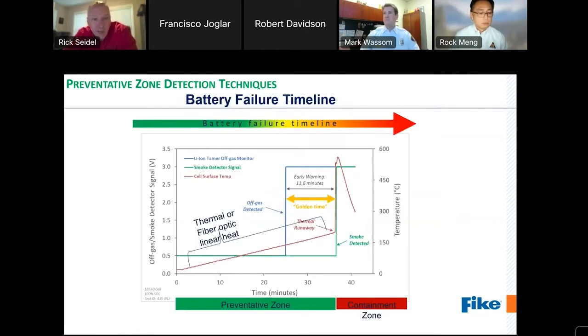Putting the battery failure timeline and preventative zone into a graphical representation, you can see that either of these techniques we discussed will give you a window of time to recognize an upset condition that may be underway, to be able to respond before thermal runaway officially takes hold or spirals out of control. Following the red line from left to right, you can clearly identify when the thermal runaway occurs by the sudden vertical spike. You can also see that there may be several minutes prior to that sudden vertical spike that preventative measures can be taken, and also that traditional smoke detection may already be too late, as traditional spot type smoke detectors likely will not sense anything until after that thermal runaway has already occurred or is in progress.